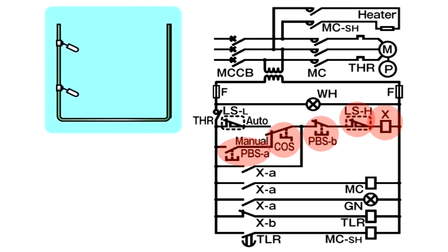As a result, X-A is turned on, and the current begins to flow from X-A to P-B-S-B, L-S-H, and to X. Therefore, even though the finger is removed from P-B-S-A, X continues to be excited. This state is known as the self-holding state of X.